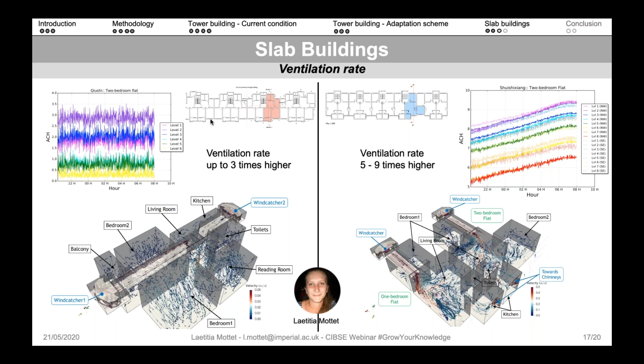The design based on one wind catcher on one side of the building and chimneys on the other side was able to increase the ventilation rate by about 5 to 9 times, which is quite a lot actually.